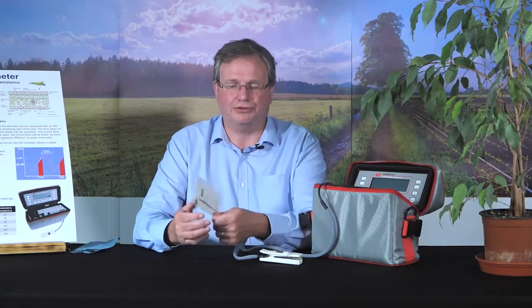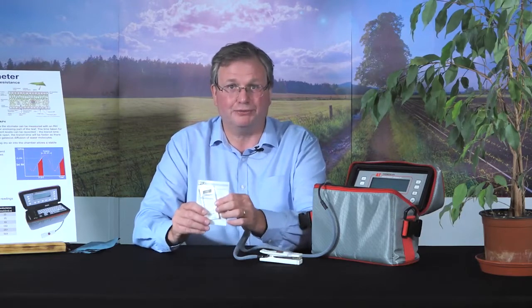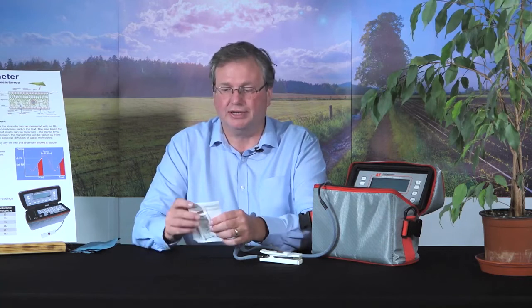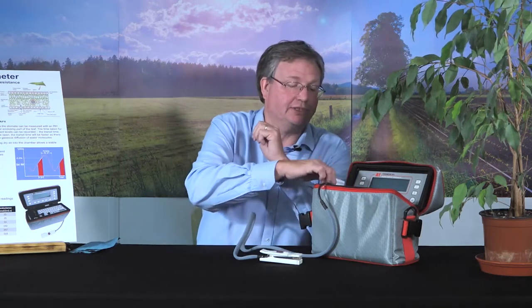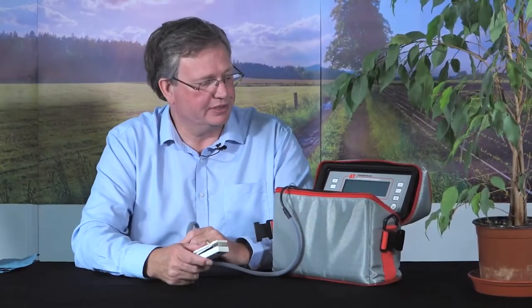We'll put the calibration plate back into the pouch. And as I said before, it'll stay fresh and usable for a day or two. I recommend making a fresh one at the start of each day and leaving it in the box, in the case. If you need to recalibrate during the day, which you will, because from morning to evening temperature and humidity is going to change, you'll need to recalibrate when you're prompted. And the Porometer will prompt you when this is needed.